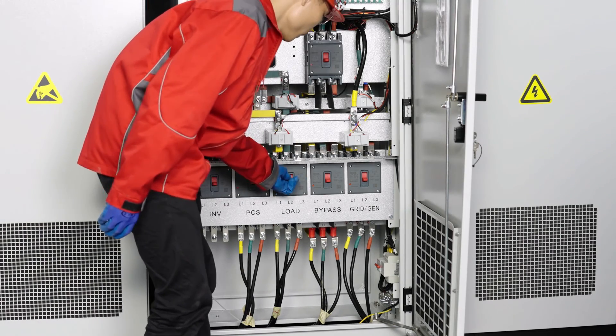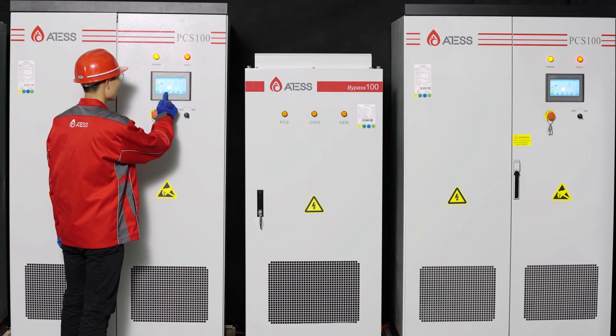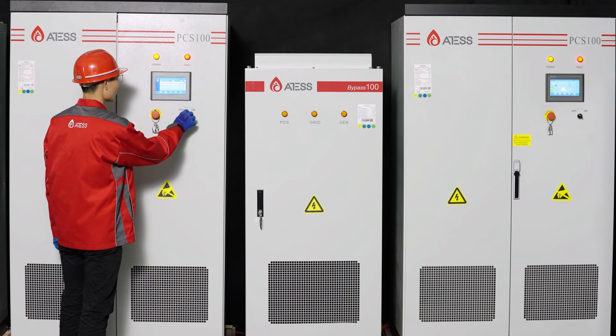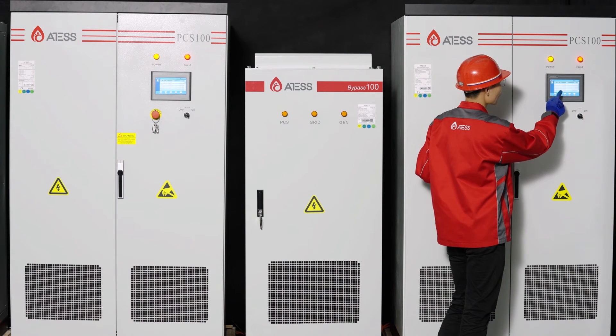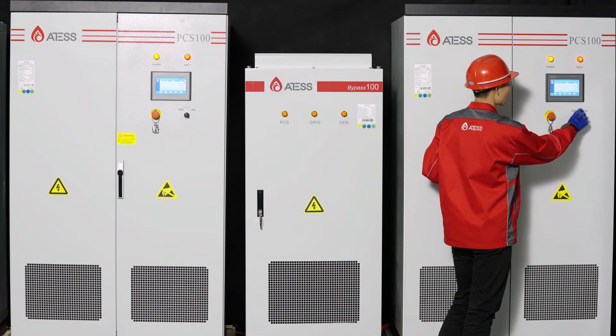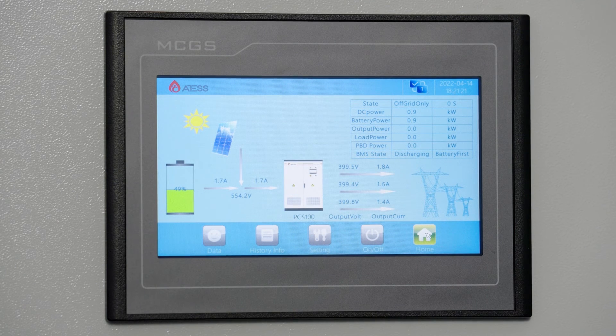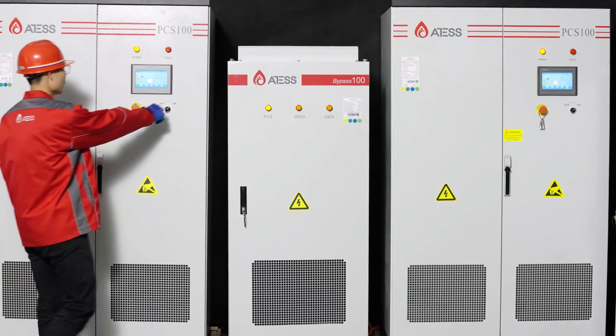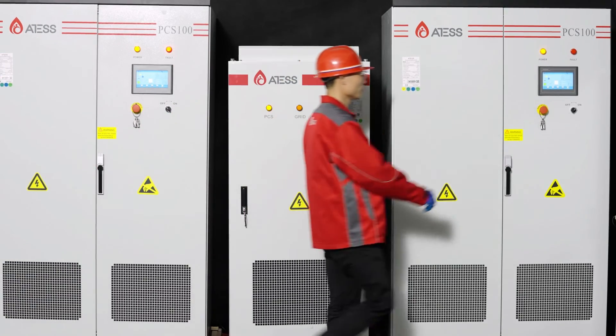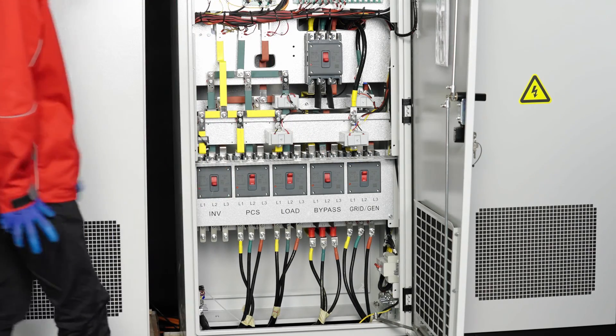Switch on the PCS and load breakers of the two bypass cabinets. Check whether the data page of the two PCS is normal and check the fault information page for communication faults or other issues. If no faults, turn the knob and click the power button on the screen to start the machine. Observe the displayed load power difference between the two PCS — if there is a great difference, please contact ATESS. Turn the startup knobs of the two PCS to OFF to ensure they enter the fault state. Switch on the power grid breakers of the two bypass cabinets.